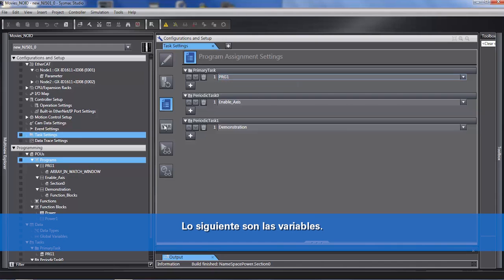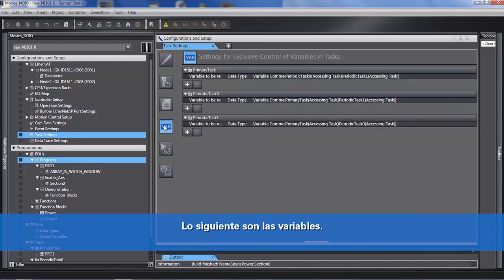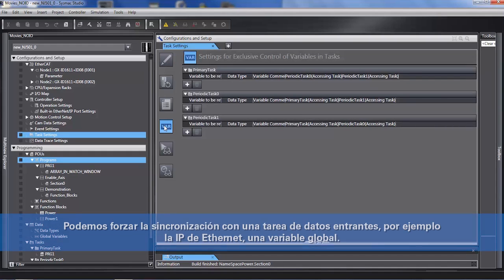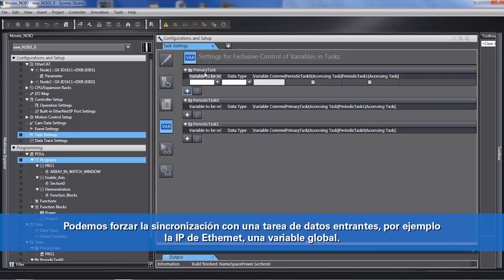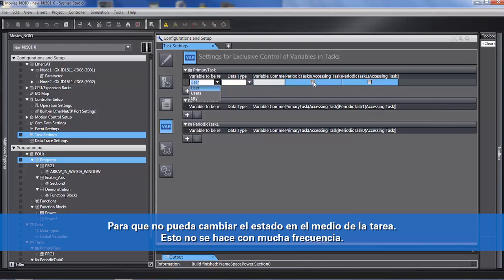The next thing is variables. Global variables are considered IO. So you can force the synchronization of data coming in through, let's say, Ethernet IP — a global variable — to a task, so that it cannot change state in the middle of your task. This isn't done very often.